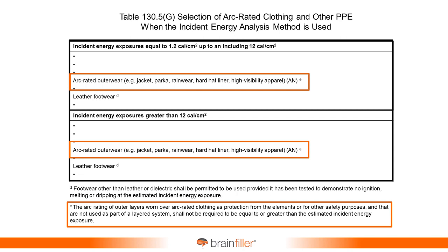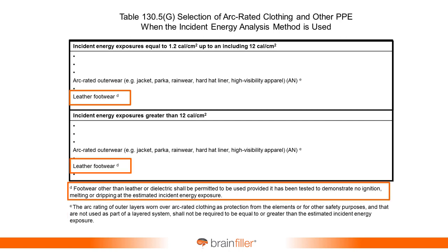That would have just been difficult. If you're wearing like a 65 calorie system, how do you get a high-vis vest to have that kind of a rating? Then we also have the reference to leather footwear. This is where we now have the ability that you can wear something else if it's been tested to demonstrate no ignition, melting, or dripping at the estimated incident energy exposure.